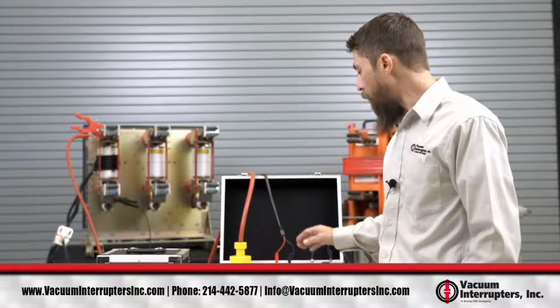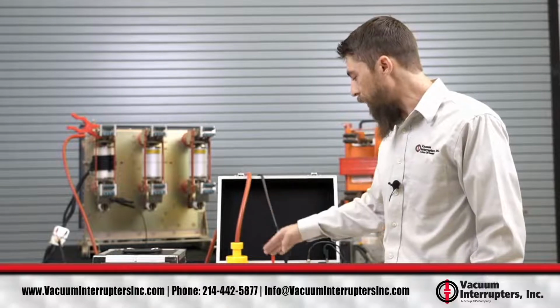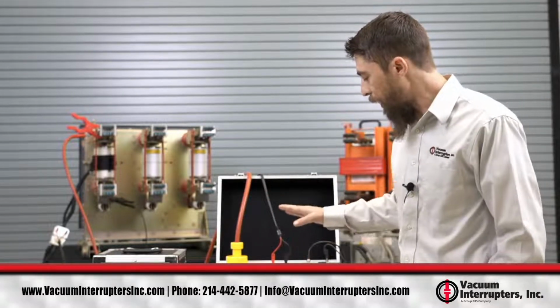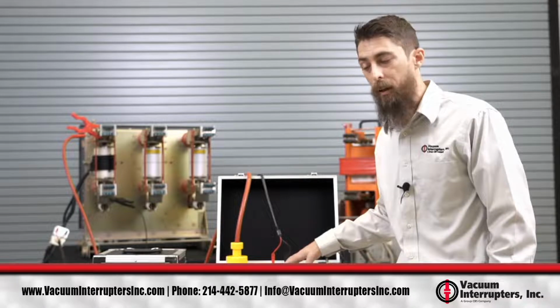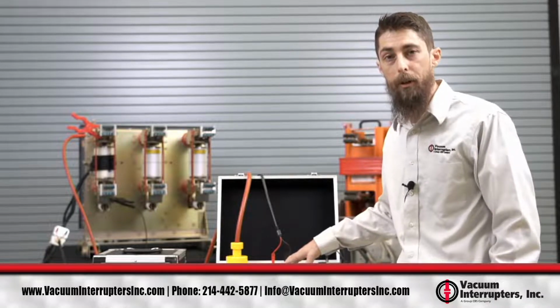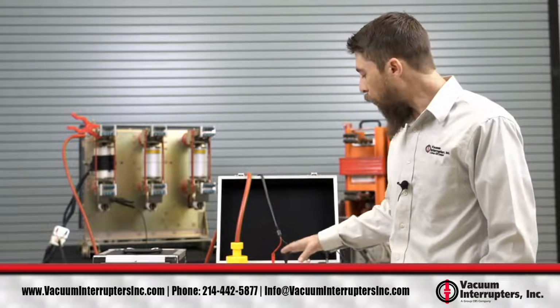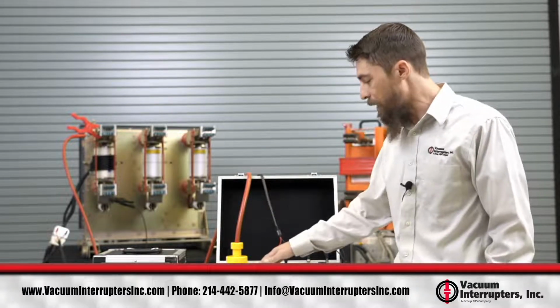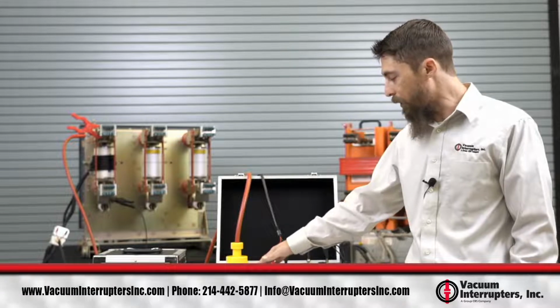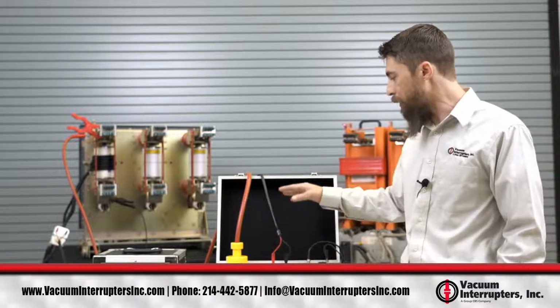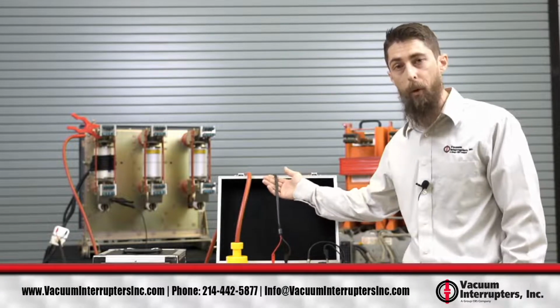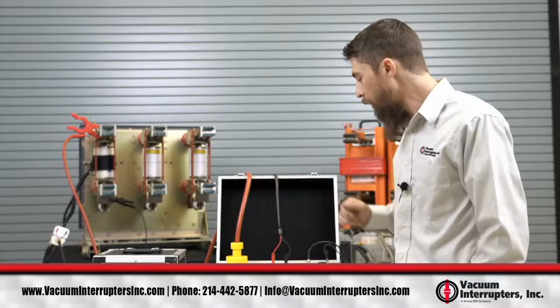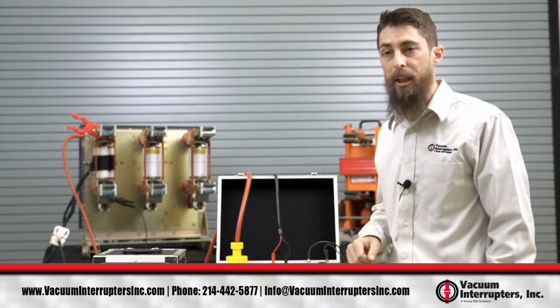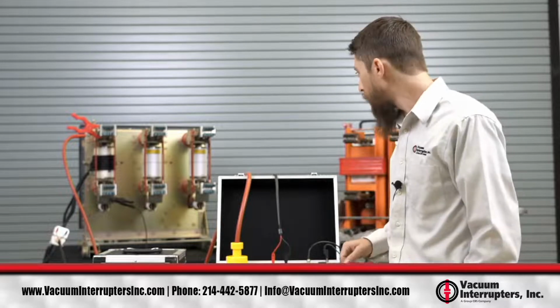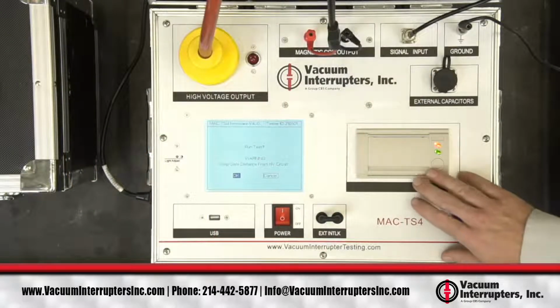Then after the high voltage has been applied and the leakage current's measured, it's going to charge a bank of capacitors inside, because we need quite a bit of power to produce a strong magnetic field. Once the capacitors are fully charged, it will apply the high voltage a second time. While the high voltage is being applied the second time, it will discharge those capacitors to the magnetic field coil, which generates the magnetic field. The whole test only takes about 1 minute to run through. So without further ado, we'll get started.